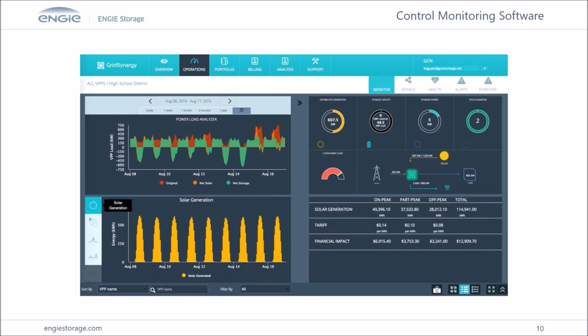The red is where you're seeing the solar is offsetting some of the load, and if you look closely, you'll see some of the orange, which is where the battery system is deploying to reduce peak demand charges or arbitrage. If you look closer, you can see there are blocks in the afternoon where there's a chunk in the green, and that's where there's a demand response program that the batteries are being utilized for. This also can show you solar production, how the two of them work together.